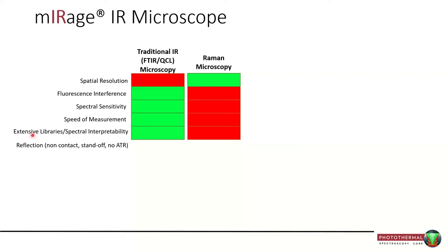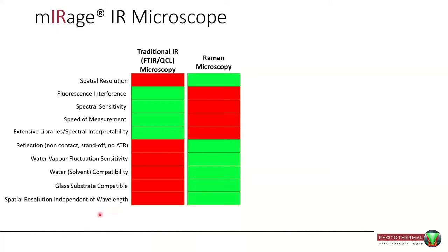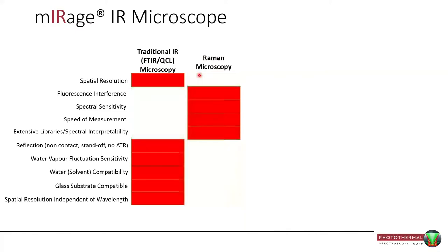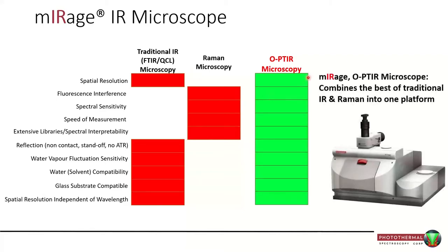For reflection mode, non-contact standoff operation, Raman is the preferred mode — IR isn't great for that. Water vapor can be a big issue in IR, not in Raman. Water and solvent compatibility for live cells is typically an issue with traditional IR but not so much with Raman. It's no surprise that most labs have two instruments — an infrared and a Raman. With OPTIR, we take the best of both and combine them into a single platform — almost literally combining the best of traditional IR and Raman.